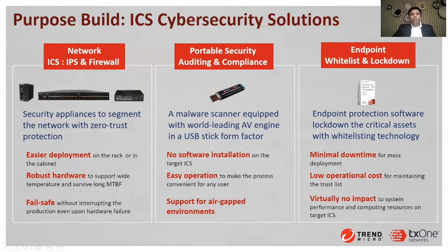And the final approach is using our whitelisting and lockdown. Antivirus gets big pushback from the operations teams as well, because it requires antivirus definition updates, and the scanning takes much longer. The alternative approach is deploying whitelisting software on the systems, like an HMI running Windows, where we can whitelist the entire system and say whatever is running on the system is perfectly fine after scanning for viruses using TMPS3. And then if no infection is found, we just lock it down.